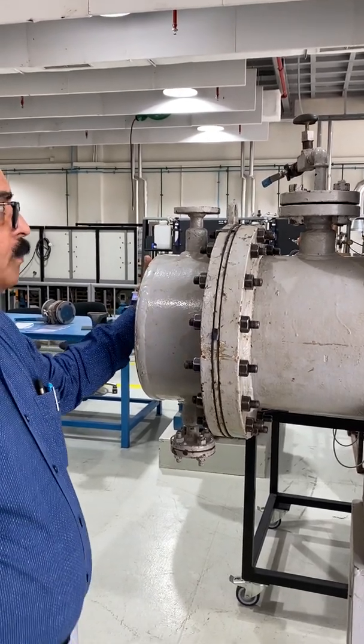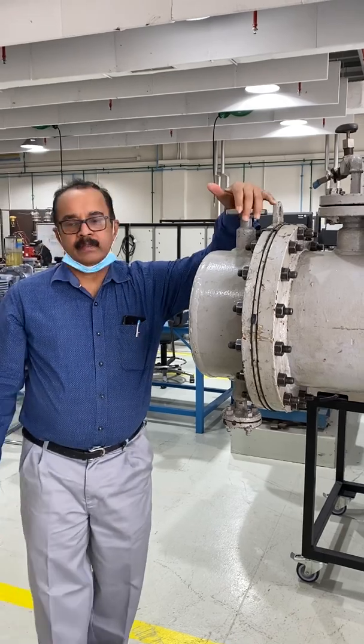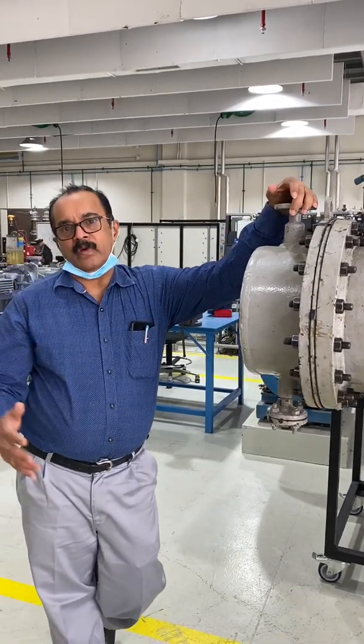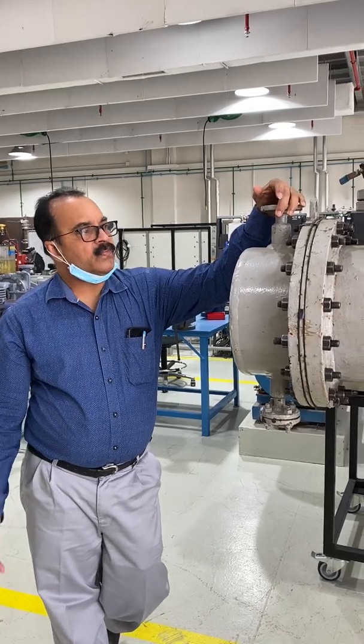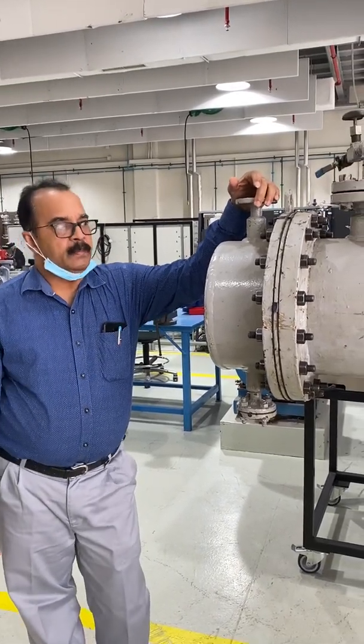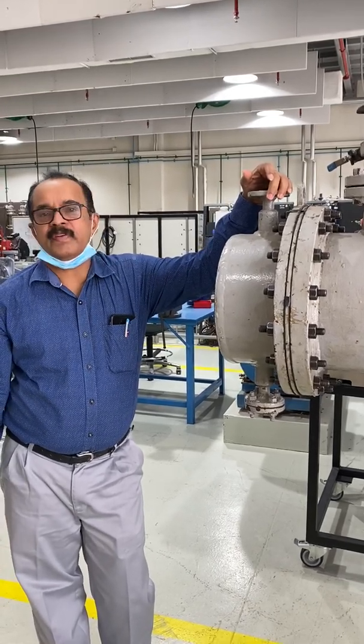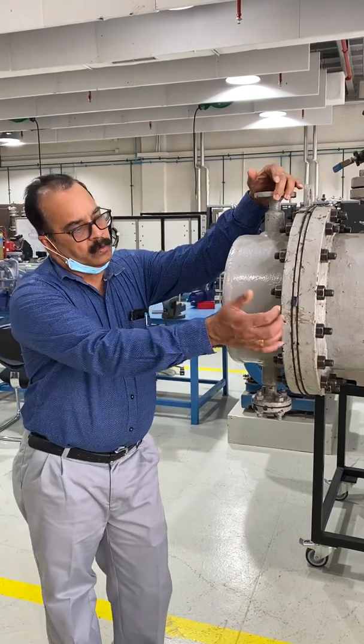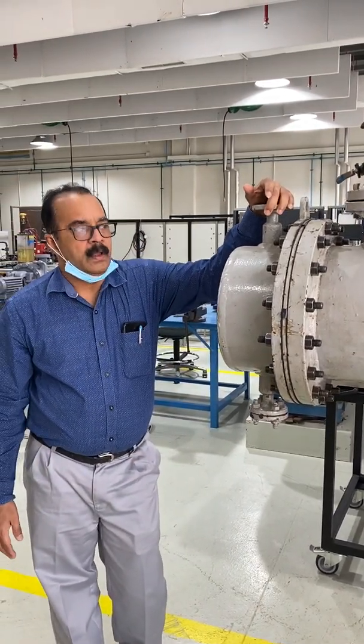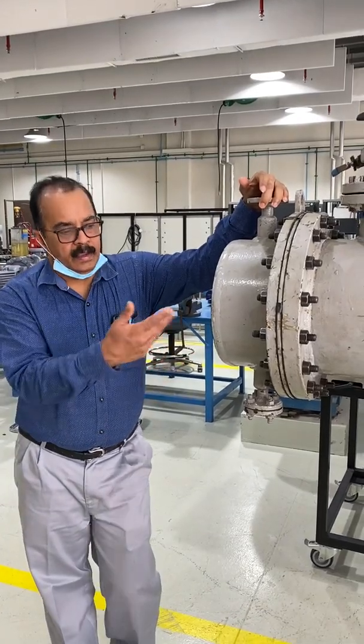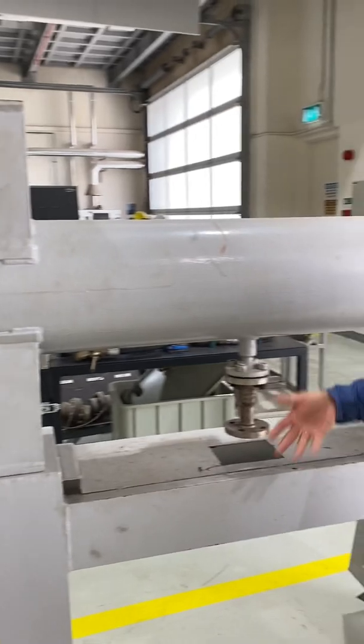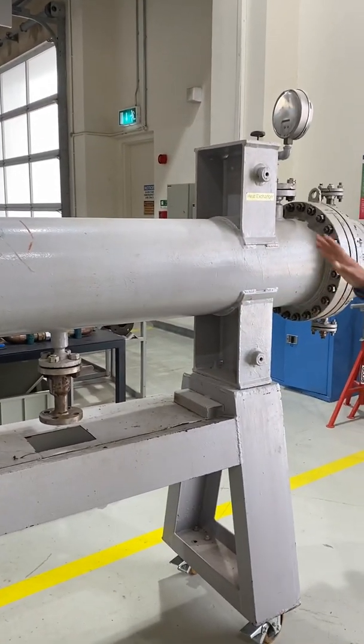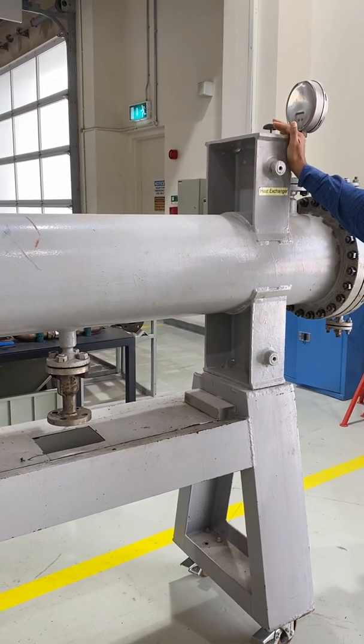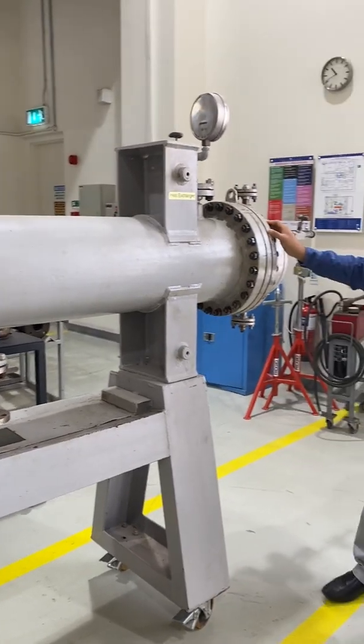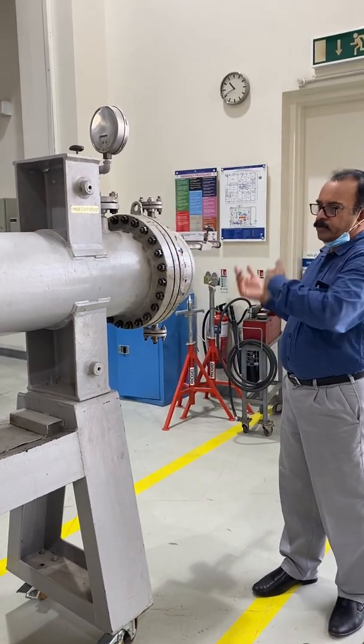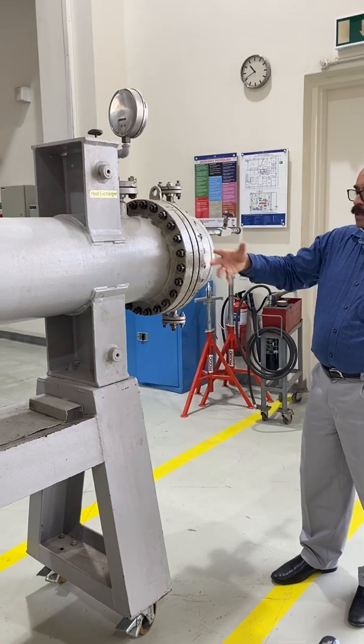This is the type of maintenance you do on all heat exchangers. The main thing is cleaning, because after using it for six months or one year, a lot of debris and dirty particles will be stuck inside, and that will reduce the efficiency of the heat exchanger. So you need to open this. Before that, you need a hot permit, because the hot fluid will be there. Every liquid will be drained through here, and once it is drained, you can take it to the workshop and start dismantling the head portion, then the tube sheet, remove that side also, and then take the tube bundle out using a crane.